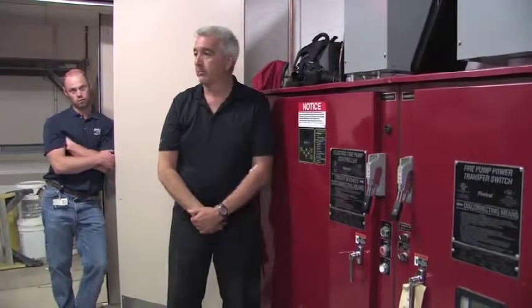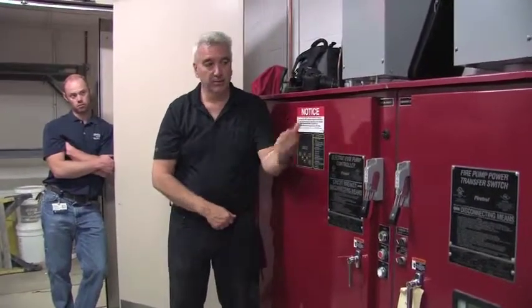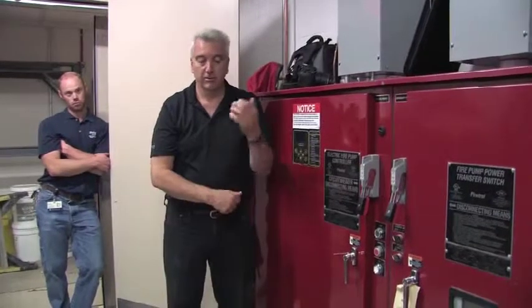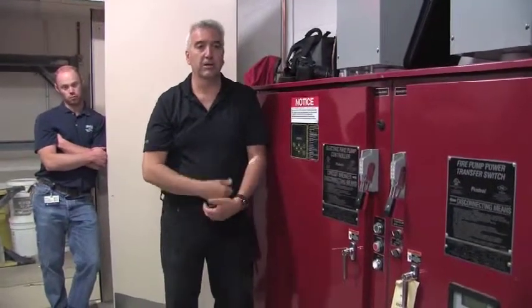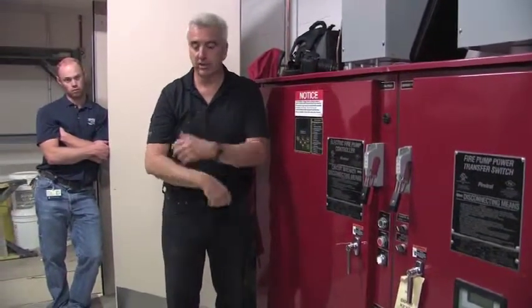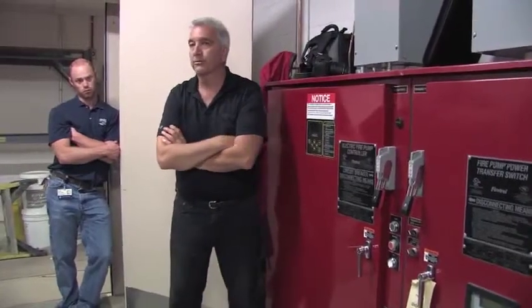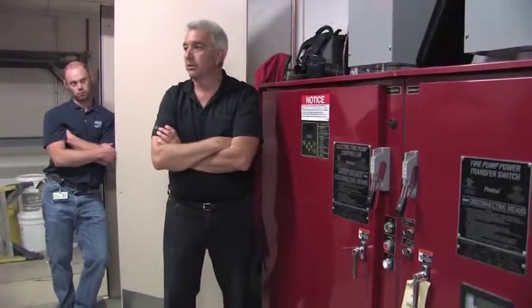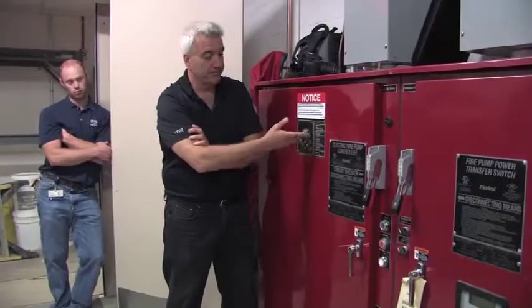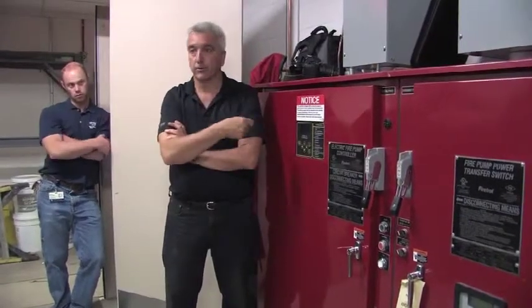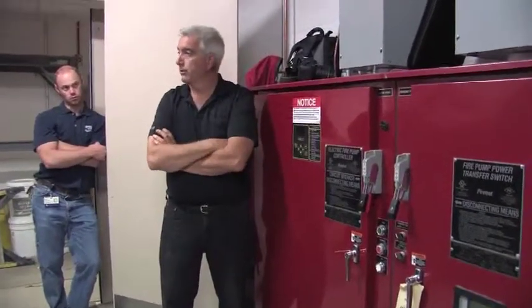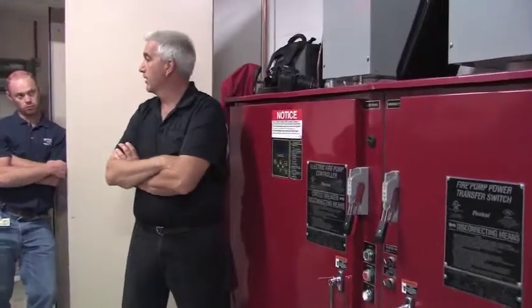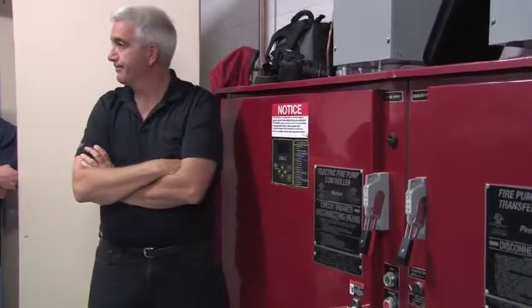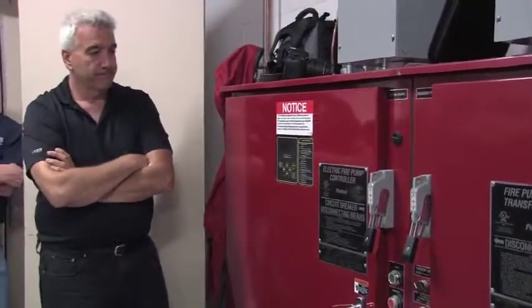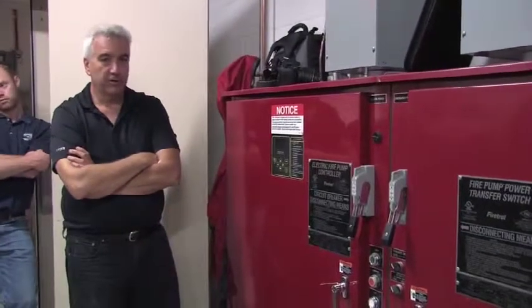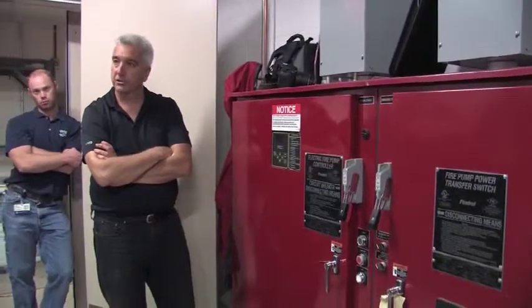So I like to use a pressure drop to simulate the sprinkler head opening, which starts the jockey pump. That way you can see where the jockey pump starts, write your settings down, and let it go a little further until the main pump comes on. What's nice about the digital displays is that you can just use one of them for your real pressure instead of looking at a mechanical gauge somewhere in the system. So far, so good? Any obvious questions?